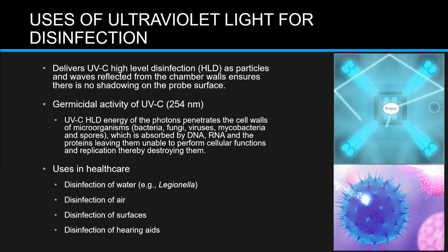So let's talk and focus first on ultraviolet light here. Ultraviolet light is a high-level disinfectant as the particles and waves are reflected from the walls of the chamber to cover the surface of the probe. And this is done at a germicidal wavelength of 254 nanometers. So at this wavelength, the energy of the photons penetrates cell walls of microorganisms, all microorganisms. It's absorbed by DNA, RNA, and the proteins, essentially destroying them and leaving them unable to perform their cellular functions, and therefore that pathogen is no longer capable of causing human infection.